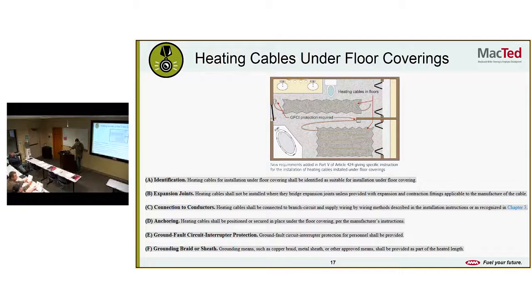Connection to conductors. Heating cables shall be connected to branch circuit and supply wiring by wiring methods described in the installation instructions or as recognized in Chapter 3. Anchoring. Heating cables shall be positioned or secured in place under the floor covering per the manufacturer's instructions. Ground fault circuit interrupter protection for personnel shall be provided. And grounding means such as copper braid, metal sheath, or other approved means shall be provided as part of the heating cable. Anybody ever put these under carpet?